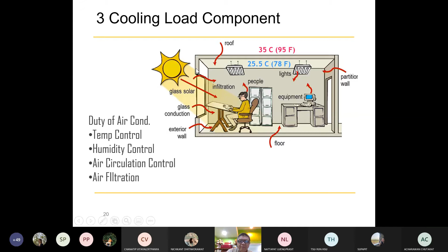The load inside is normal - people is easy, for an adult I can say one person is 700 BTU, and equipment we can use like 1.5 watts per square foot or something like that. I think the critical part is the infiltration, ventilation, and all the walls we select when we design. We have to be careful on the insulation or heat transfer between the roof or the walls also.